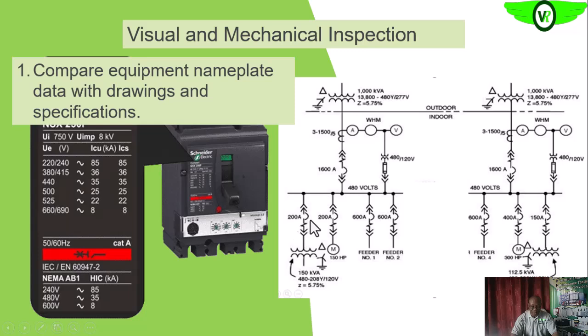Take this detachable circuit breaker, it's 200 amps. Looking at the voltage of the bus, it's 480 volts. So the circuit breaker you use should be able to work comfortably in that environment, that is 500 volts or 480 volts AC.